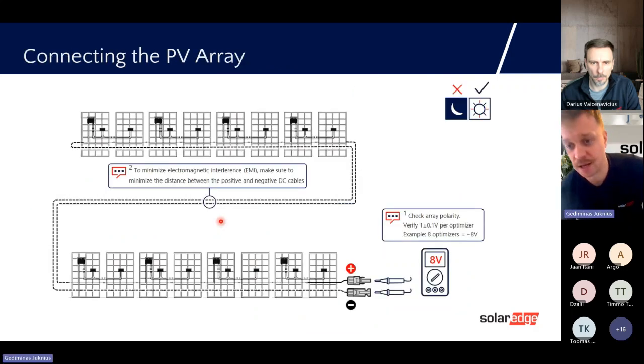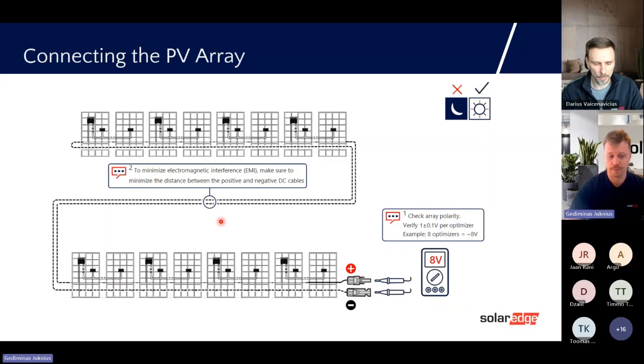Okay, another thing, a small remark for the Nordic countries. When you do an installation, you can always check the voltage to see if you have connected everything correctly. The story is very simple. An optimizer which is not paired, not connected to the inverter, gives you 1 volt per optimizer. Last year in November, December, even this year in January, installers come in the morning and do the installation, and by the afternoon or late afternoon they start pairing or measuring the voltage, and they don't see the right numbers. They start to check the cables, but the problem is very simple.